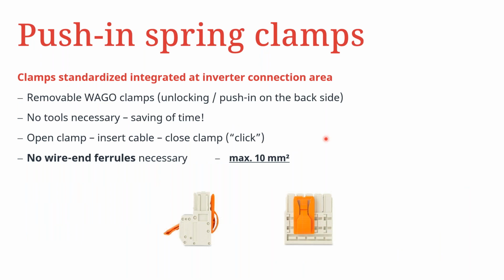Another very special aspect of the GEN24 Plus inverters is that it comes with push-in spring clamps, and these are actually removable when you're doing the installation. From the back of the clamp, you can see there is a locking and unlocking mechanism that you can press to release. This allows very fast fitting of the cables, because you just lift the clamps on top, insert the cable and lock the clamps. Once you get a click, it means that the clamps have secured the cables.